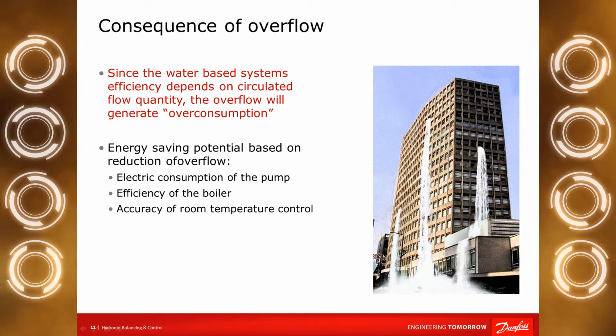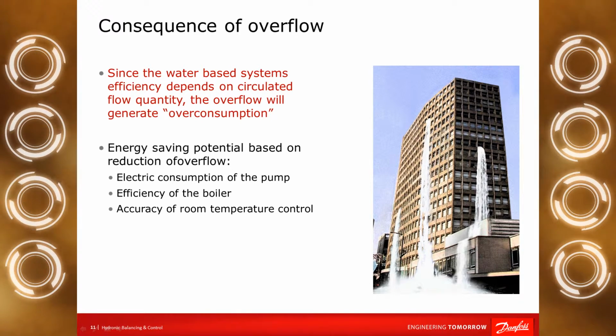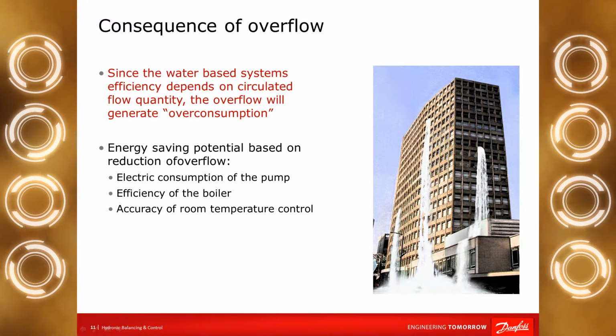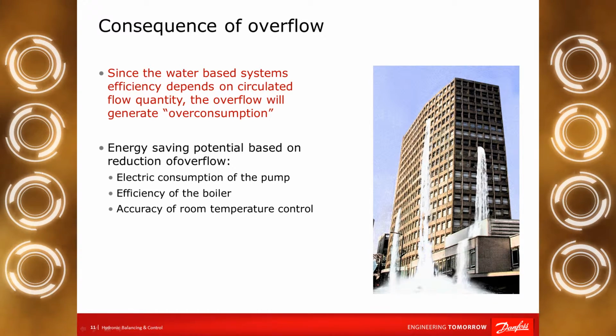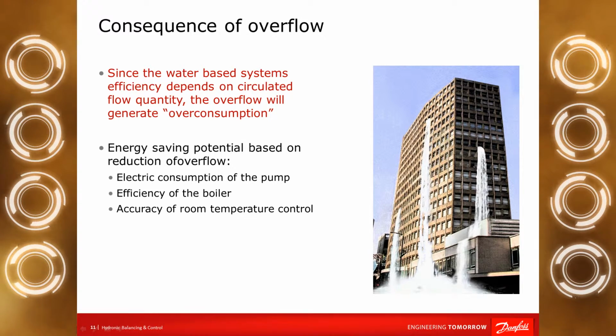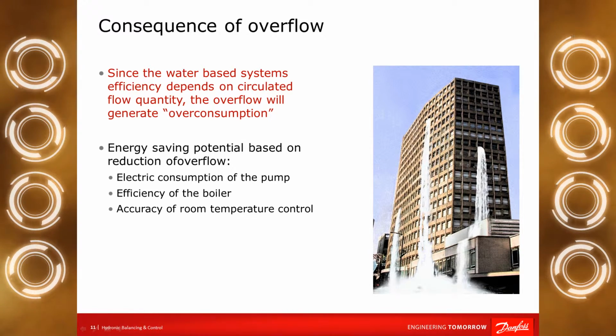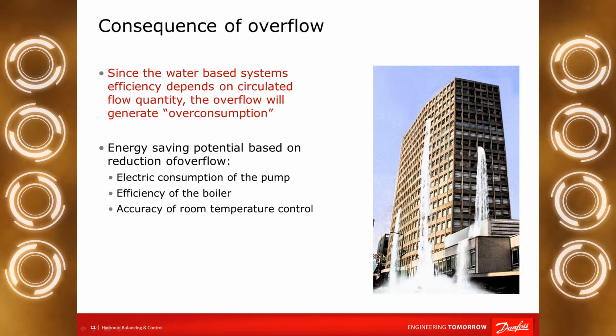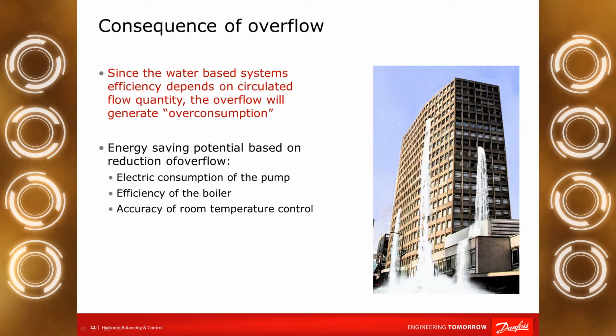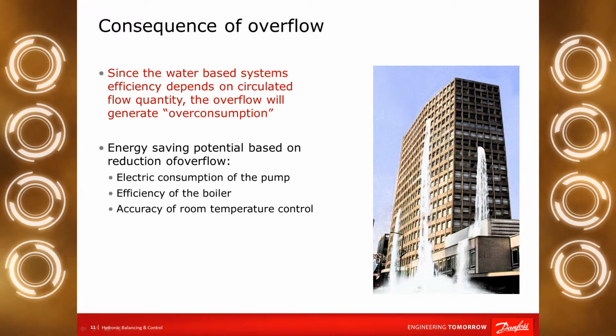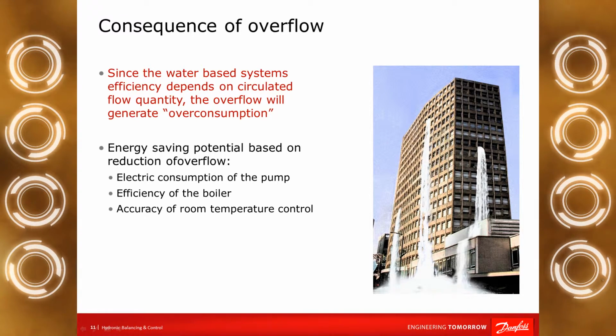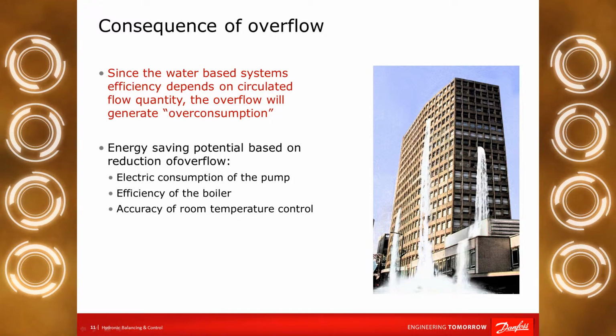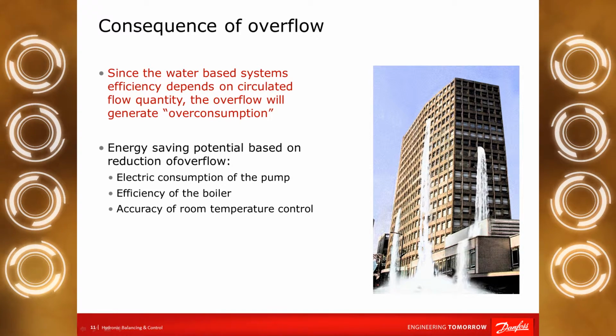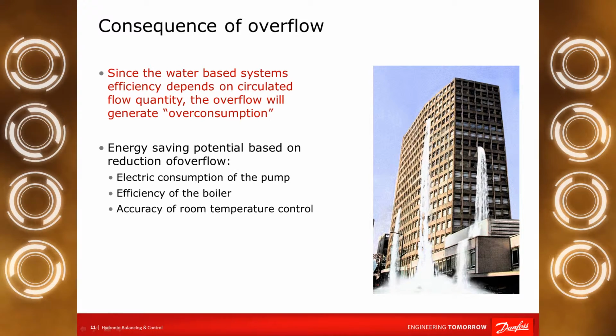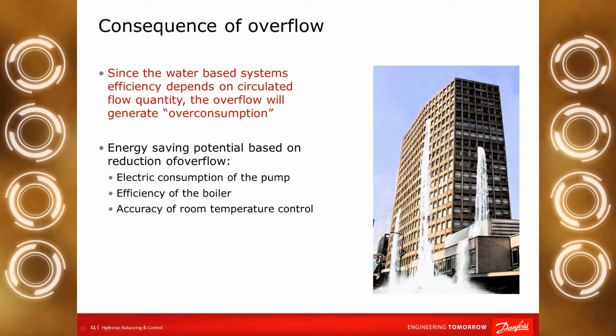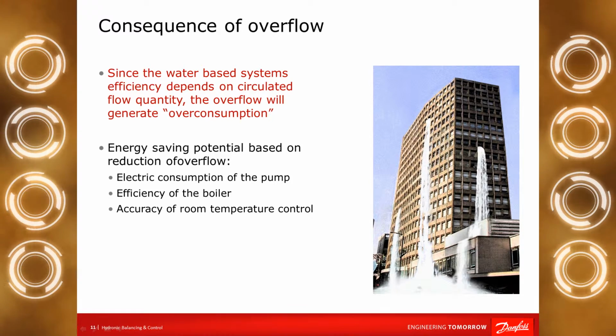Efficiency of the boiler. If we have overflow, definitely we will have lower pressure, temperature drop on the radiator. That means the return temperature will increase. If the return temperature is higher, we can use less efficiency of the chiller, or of the boiler, or the substation. If we think about the cogeneration and the district heating system, we know very well if the return temperature from the district heating system is too high, we cannot utilize the maximum efficiency of the turbines of the electricity production.